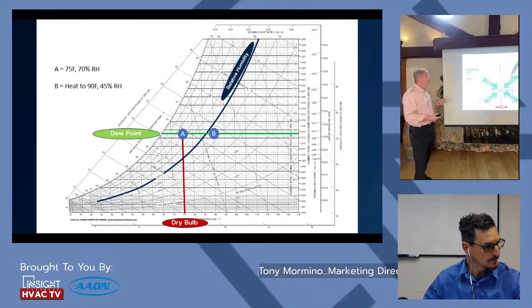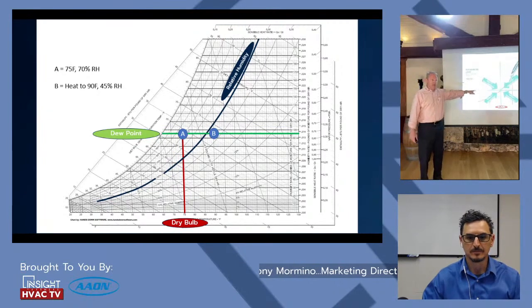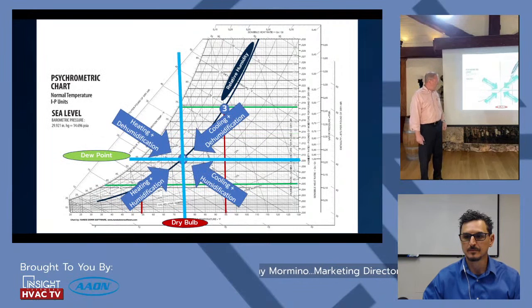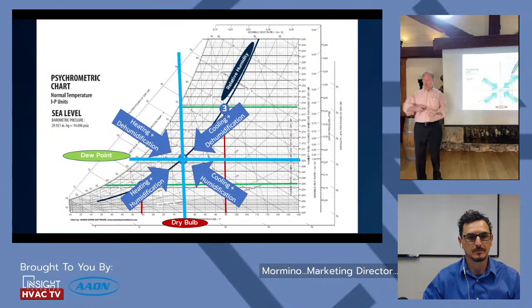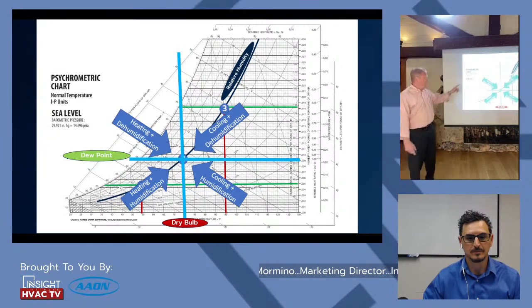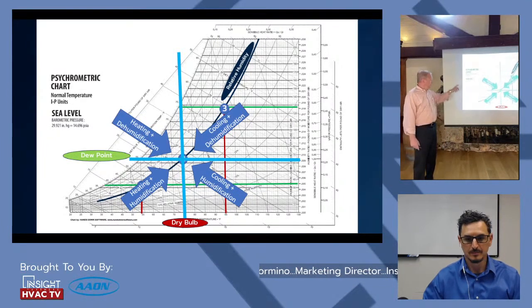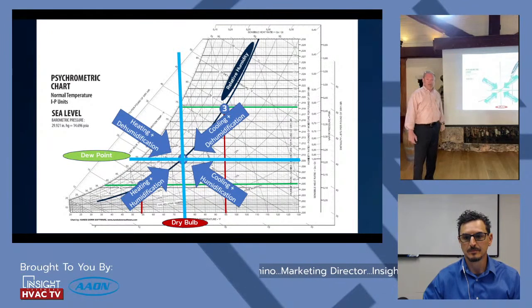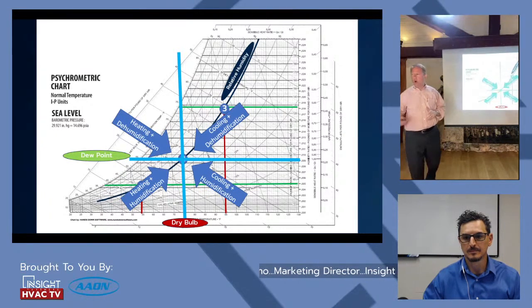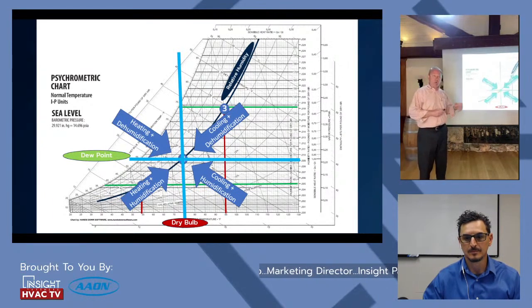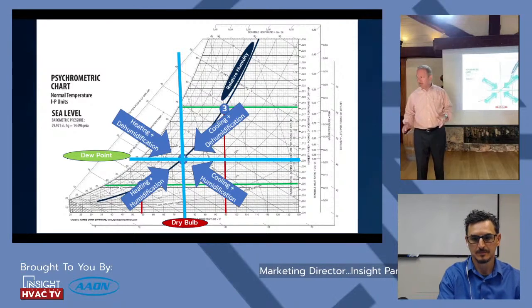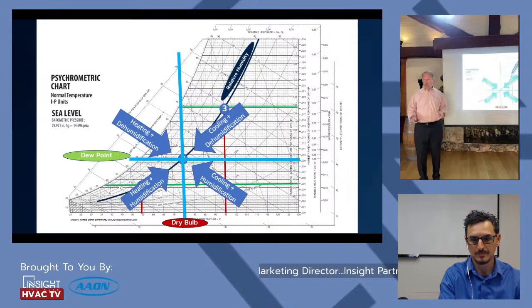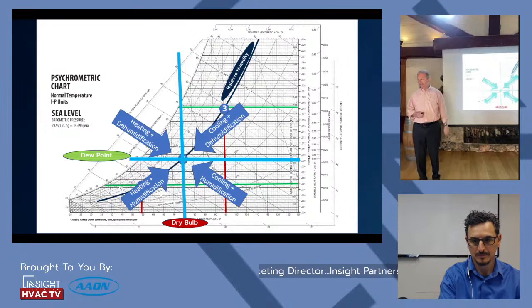Depending on where you are on the psychrometric chart, there's a central design point — typically 75°F at 50% RH. From wherever you are, it's a simple process: you're either cooling and dehumidifying, heating and dehumidifying, heating plus humidification, or cooling plus humidification. It really depends where you are on the chart to define the equipment needed. Once you know where you are and where you want to be, designing the equipment to get there becomes a straightforward project.